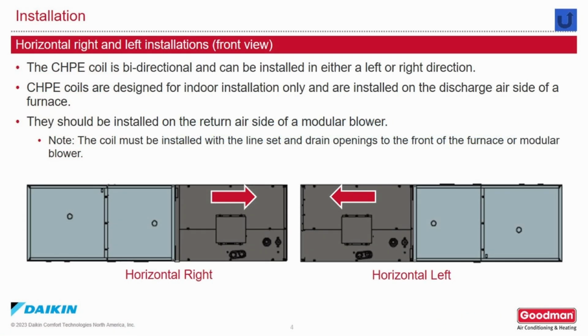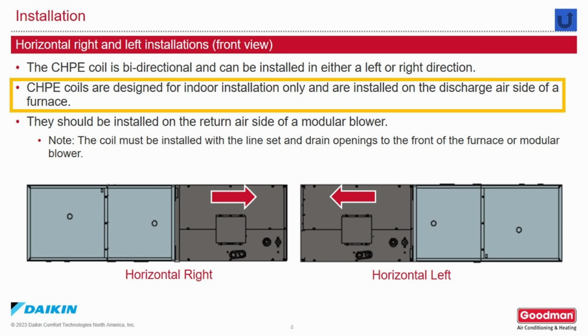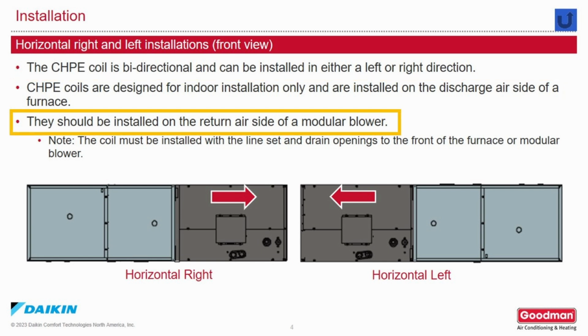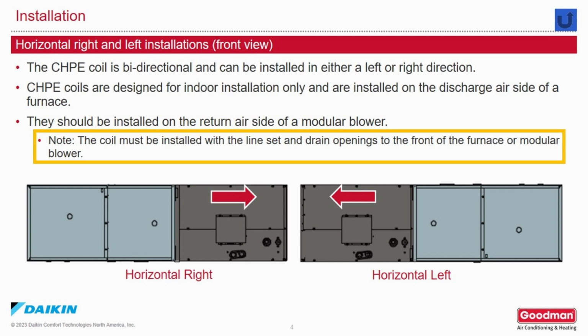For horizontal right and horizontal left installations, the CHPE coil is bidirectional and can be installed in either left or right direction. The CHPE coils are designed for indoor installation only and are installed on the discharge air side of a furnace. They should be installed on the return air side of a modular blower. The coil must be installed with a line set and drain openings to the front of the furnace or modular blower.